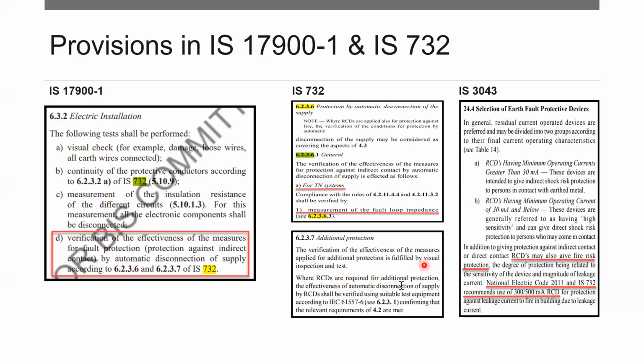Now, in case of RCDs, we all know that there are two categories available. One is up to 30 milliamps, where these devices are for direct shock risk protection to the persons who can come in direct contact. And those above 30 milliamps give indirect shock risk protection to the persons in contact with the earth metal. RCDs also offer fire risk protection, and according to the National Electric Code 2011 and the IS 732, both 300 and 500 milliamps RCDs can be offered for protection against the leakage current to prevent fire in the building due to leakage currents.